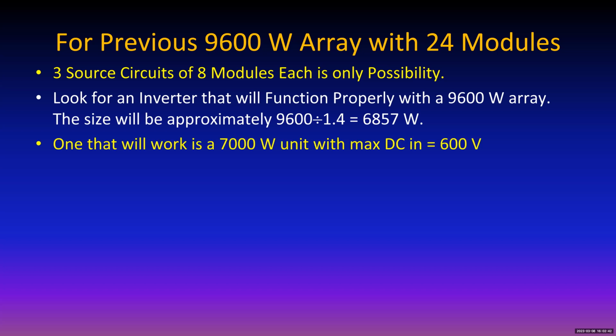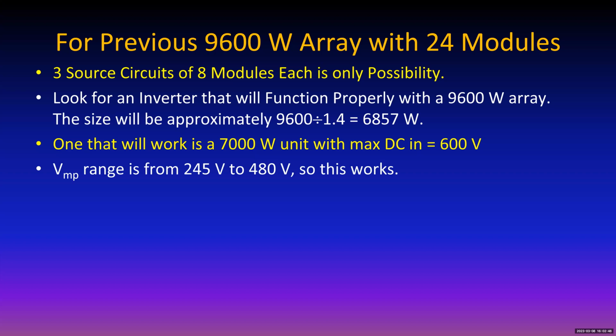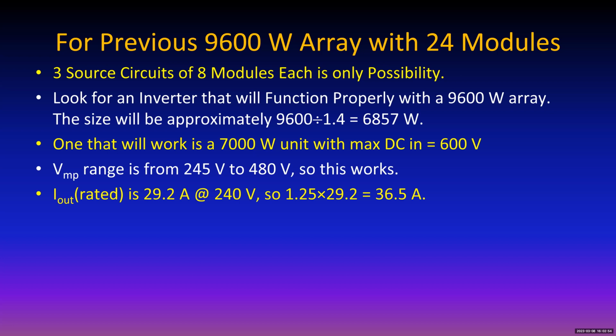Well, there is a 7,000 watt inverter that would work, so maybe we'll pick that one. It has a maximum power range from 245 to 480. That works. Output rated current 29.2 at 240. That's 36.5 amps that you have to size your wires to. You can do that. Use a 40 amp circuit breaker.